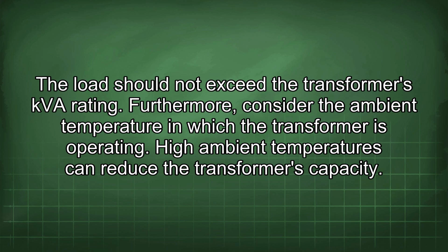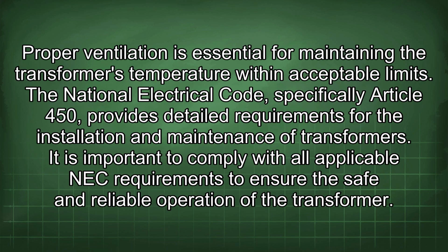Furthermore, consider the ambient temperature in which the transformer is operating. High ambient temperatures can reduce the transformer's capacity. Proper ventilation is essential for maintaining the transformer's temperature within acceptable limits. The National Electrical Code, specifically Article 450, provides detailed requirements for the installation and maintenance of transformers. It is important to comply with all applicable NEC requirements to ensure the safe and reliable operation of the transformer.